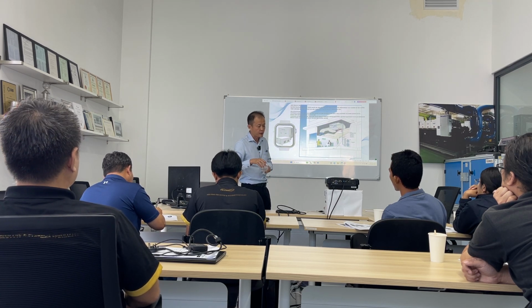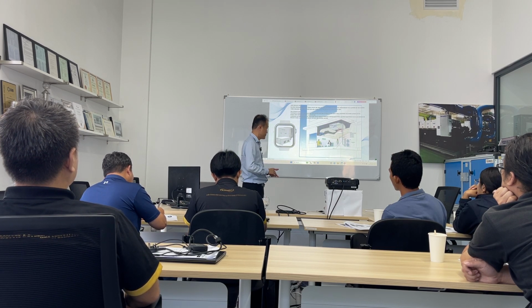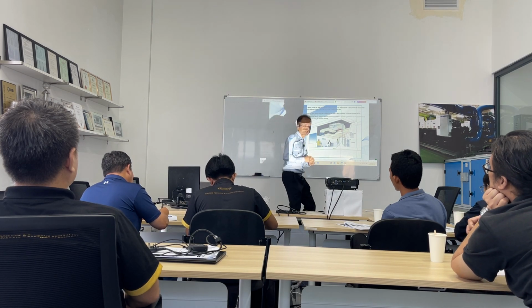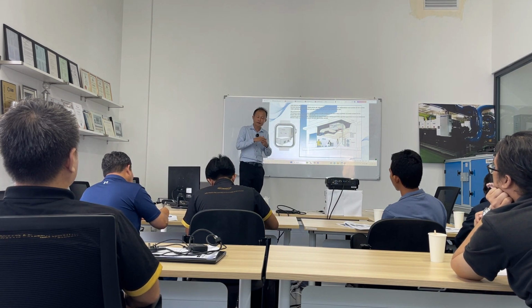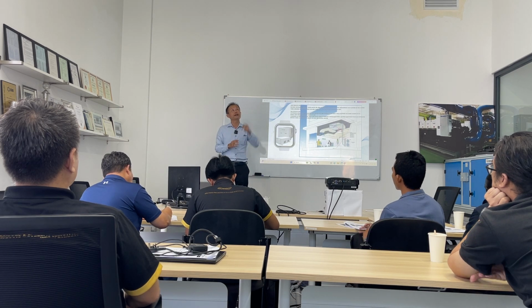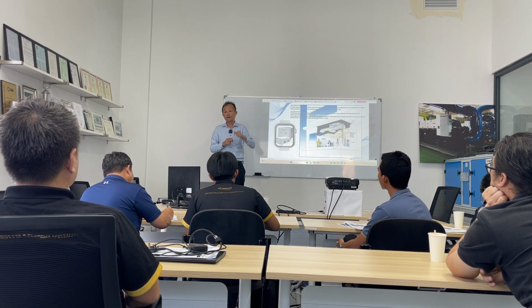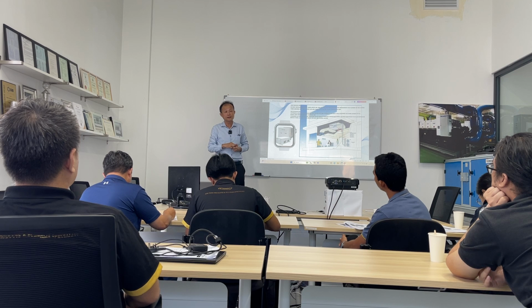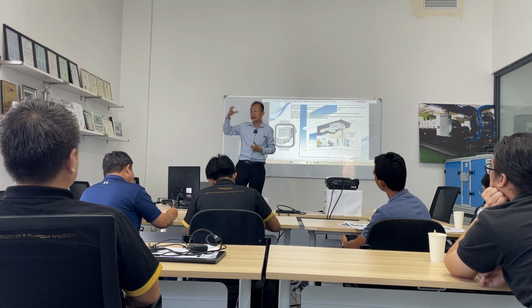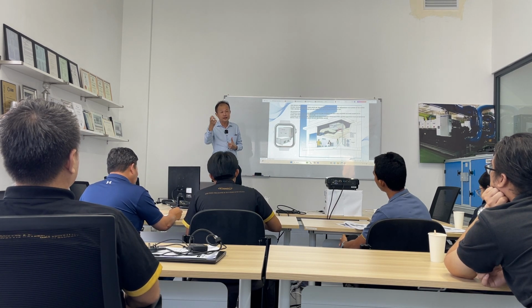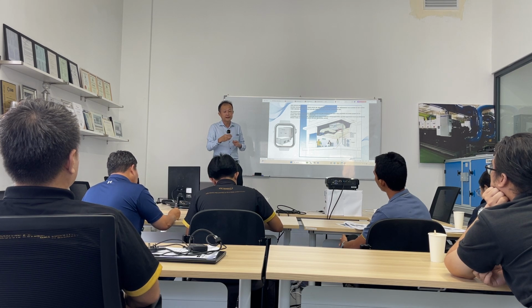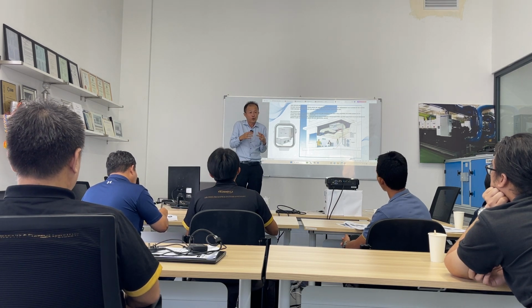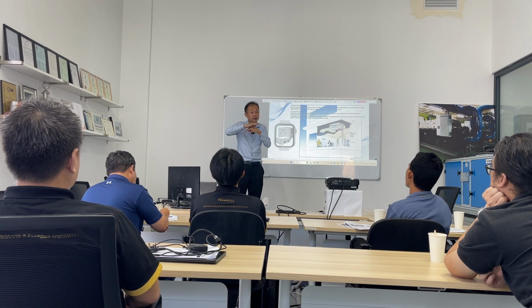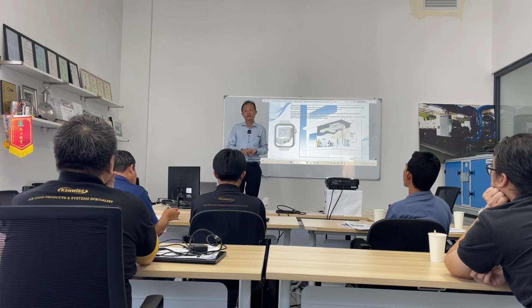Why I want to demonstrate this process by using this prop is that one of the very important processes of aircon is that the coolness of the surface of the cooling coils has to be lower than the air dew point inside the air in order to extract the moisture, so that the humidity level here is controlled well up to the level that you feel comfortable.